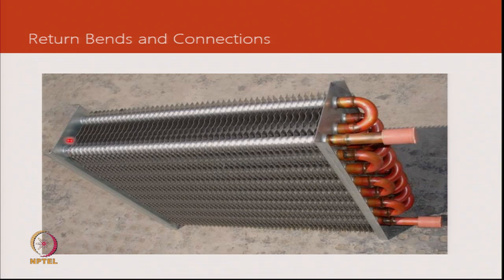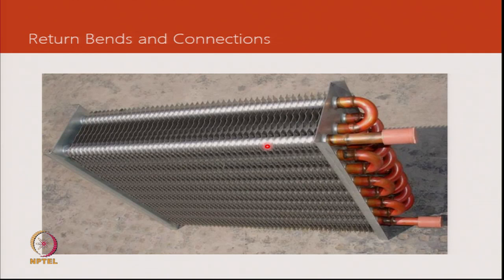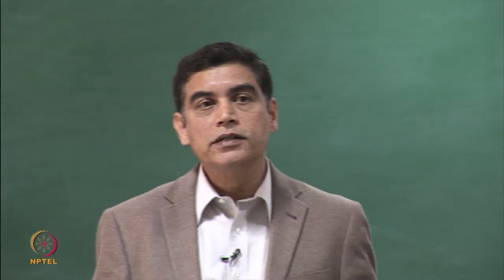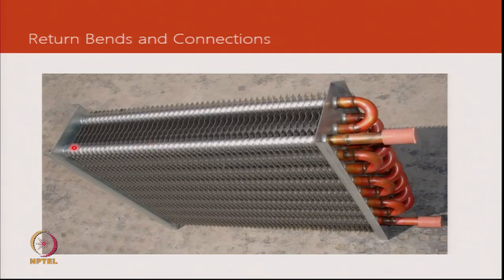Once manufactured, the hairpins are on one end and the fins are visible. The fin spacing on this particular coil is much higher than in the previous mini-split example — this design is more suited to a refrigerator application or low pressure drop design. These components are referred to as return bends, and after manufacturing the coil, they are brazed in an automatic process using multiple brazing guns.